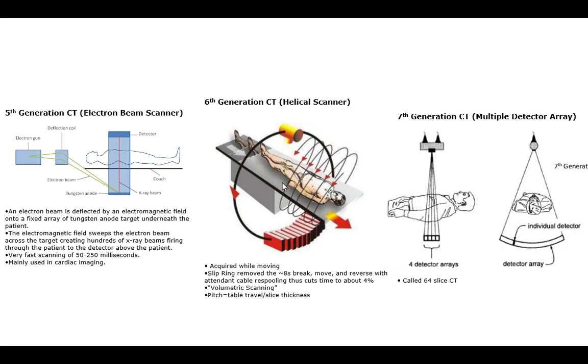But that means I'm not sampling the whole thing. I'm only sampling part of it. But because of the overlap, I can often get the same quality as the original, but give you a lower dose. But that's on the reconstruction. I can then try to subsample that down so I can still have a 1-to-1 type of slice. So they can be different between how thick my slice is and how thick the sampling beam is that I'm using. That make sense?